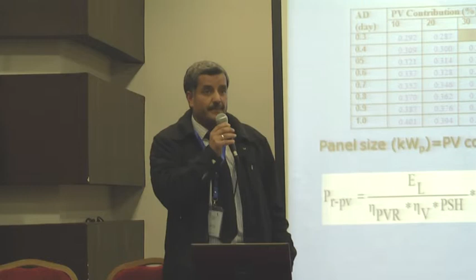As we said, the autonomy days is the period that we allow the battery to supply the load without using any source from renewable sources. We found that the minimum cost of energy production is obtained at 30% PV contribution and 0.3 autonomy days, about $0.286 per kilowatt hour.